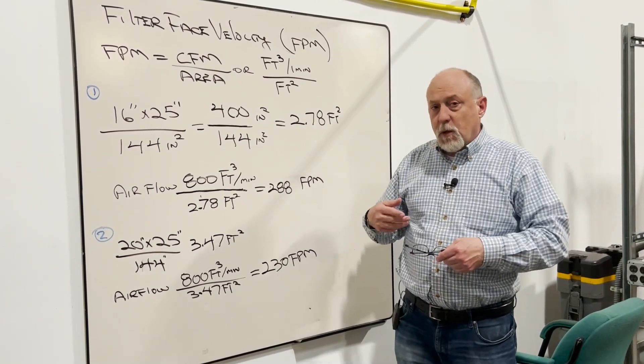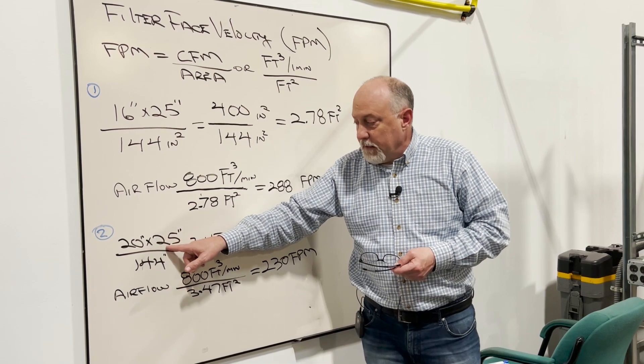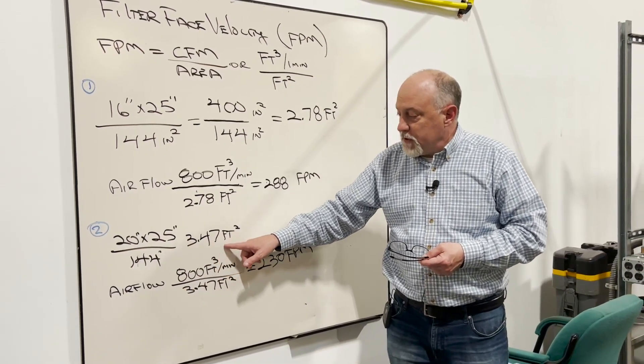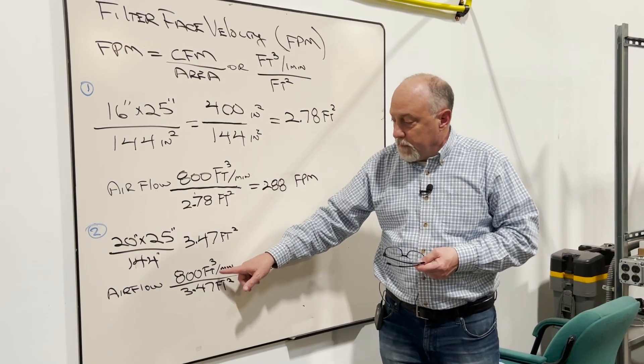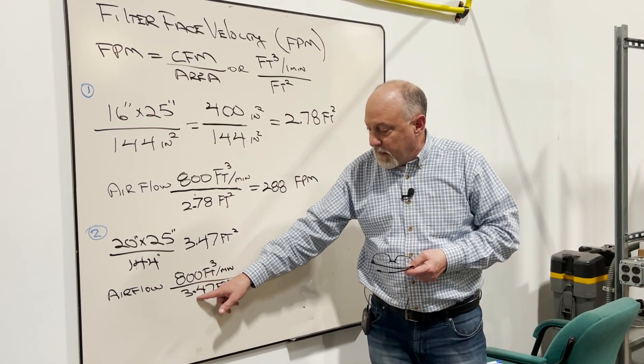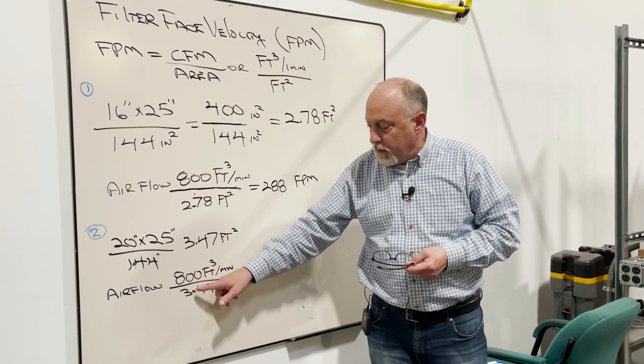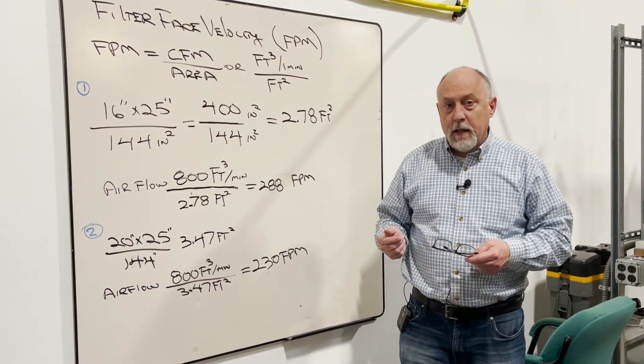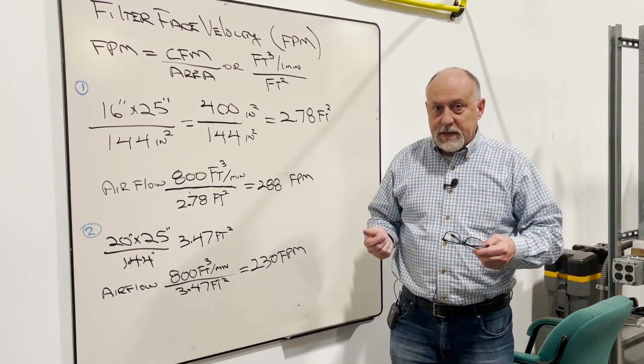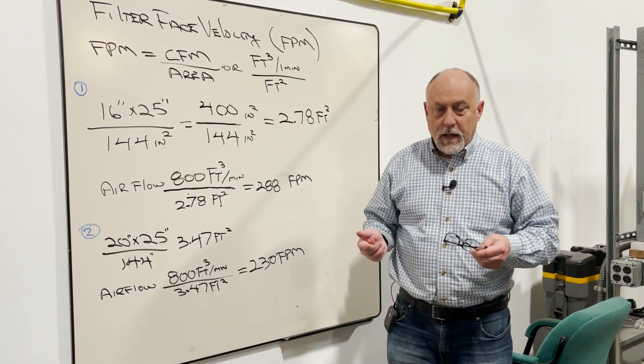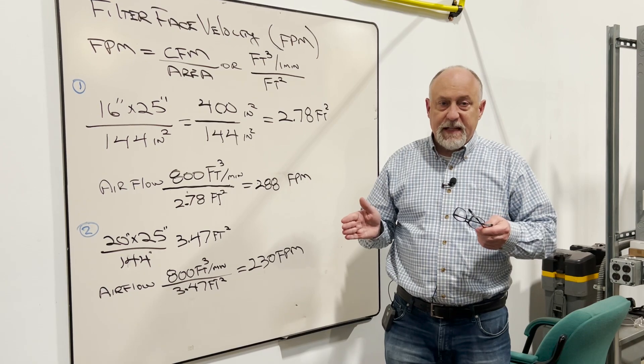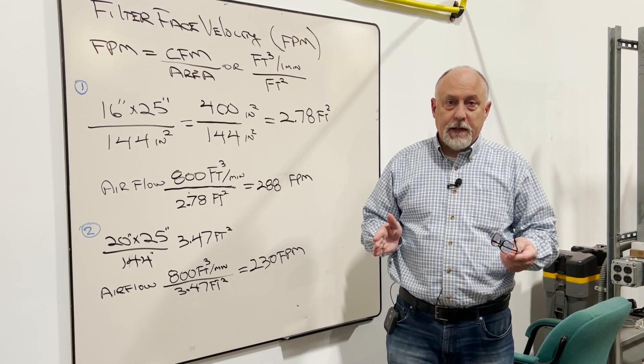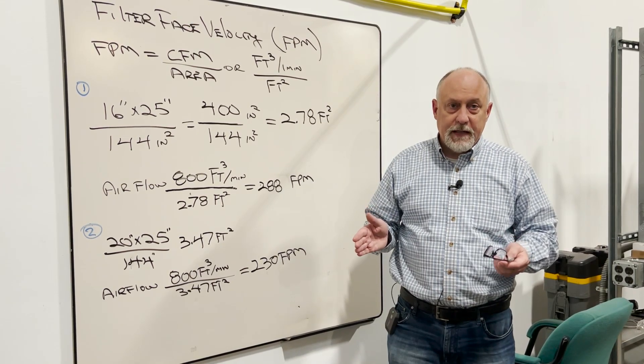What happens if we go with a larger filter? So if we take it up to a 20 by 25, divided by 144, that gives us 3.47 feet squared of area. Take the same 800 CFM divided by 3.47 — that gives us 230 feet per minute. So that slower air velocity is just going to give us better filtering. Now I said between 250 and 500 is ideal. If you go lower than that, it's really not going to hurt anything — it's just probably a little more filter media than you might need.